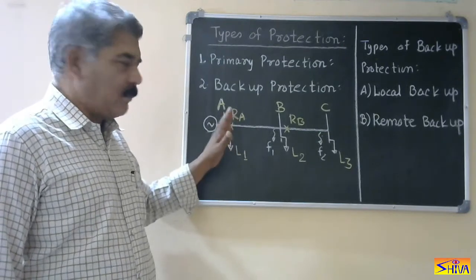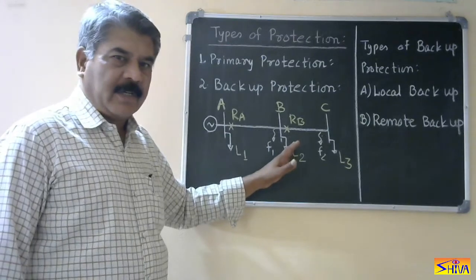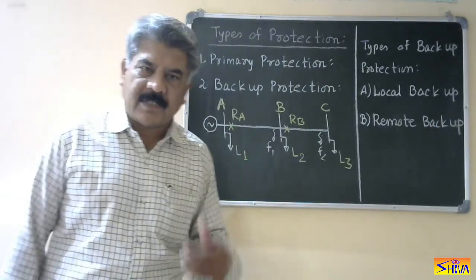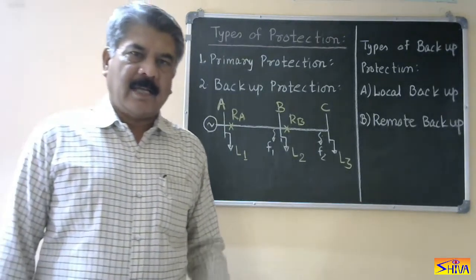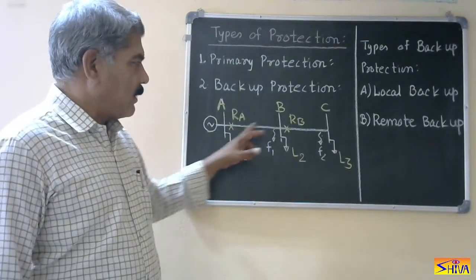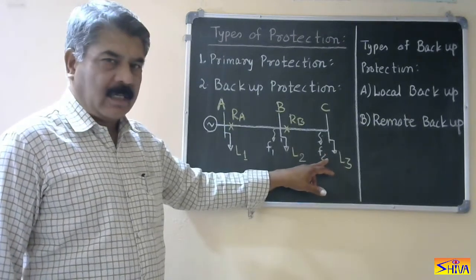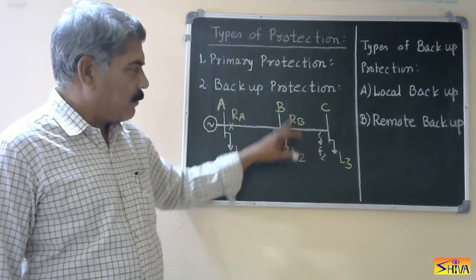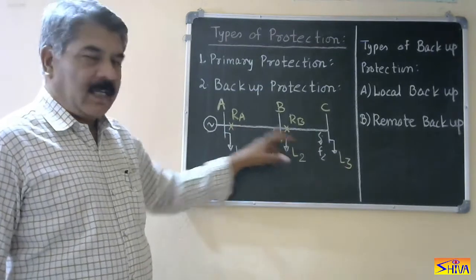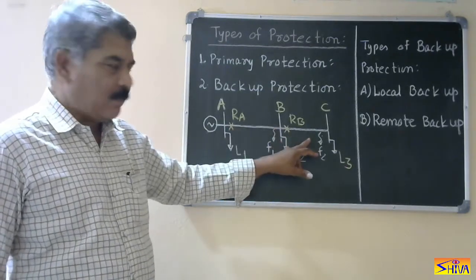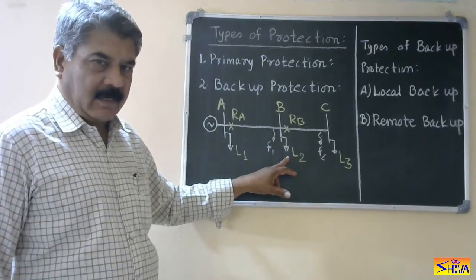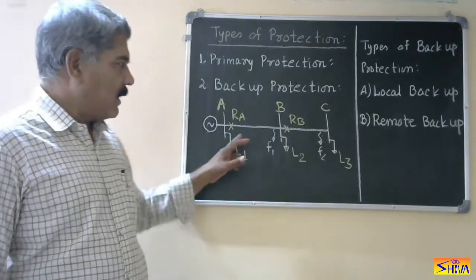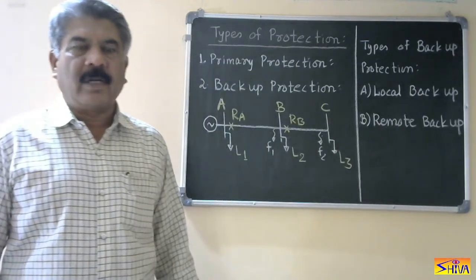The drawback of remote backup is that it has to wait for some time — when fault F2 occurs, R-B should operate first as the main protection, and only when R-B fails should R-A operate as backup. So there is a time-delayed operation; it does not operate instantaneously. A second major disadvantage is that when R-A operates for fault F2, loads L2 as well as L3 are both disconnected — a large area of the power system is disconnected when remote backup protection operates. But the advantage remains that no additional cost is required.